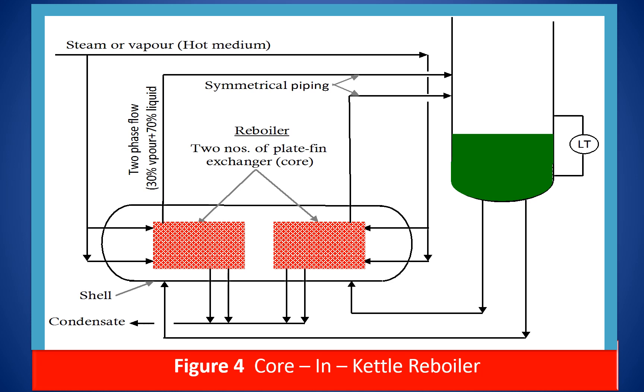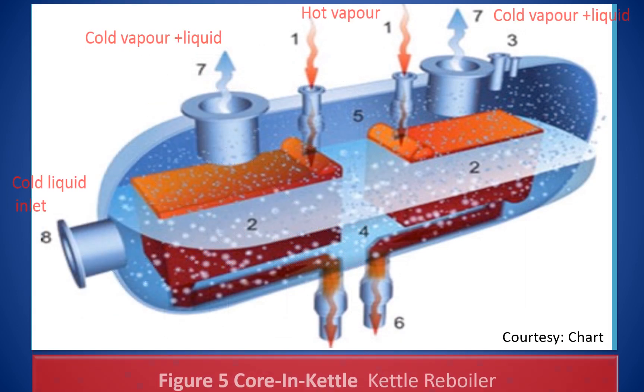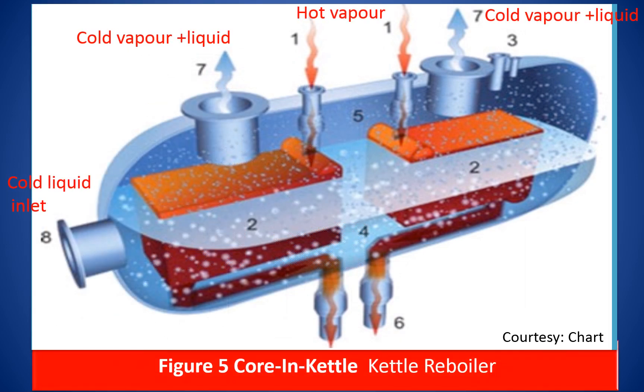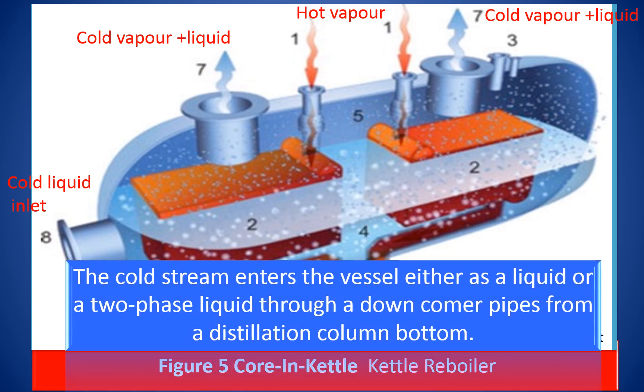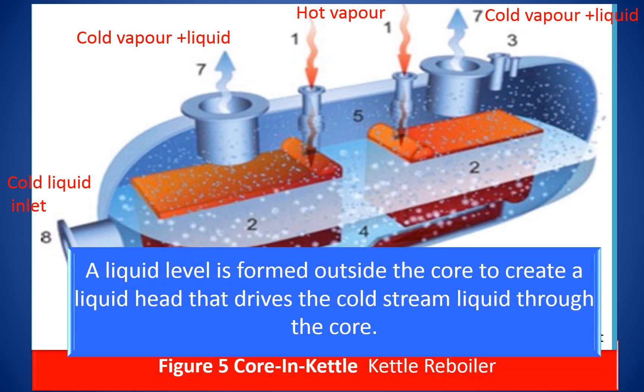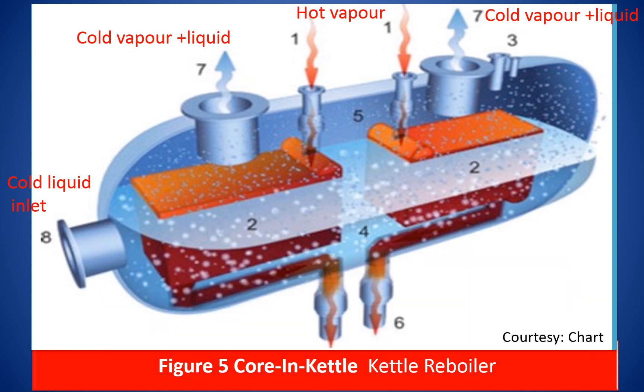Inside the heat exchangers, the warm stream cools as it flows against the cold stream from the column. The cold stream enters the vessel either as a liquid or a two-phase liquid through a downcomer pipe coming from the distillation column bottom. The liquid level is formed outside the core to create a liquid head that drives the cold stream of liquid through the core. The cooled or condensed warm stream, which is steam, leaves the core and shell as condensate. The cold stream vapor along with unvaporized liquid leaves the vessel through the outlet nozzles to the column bottom, where the liquid is separated and the vapor moves up the column.